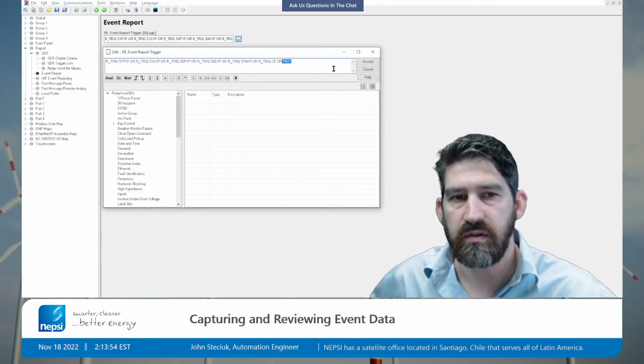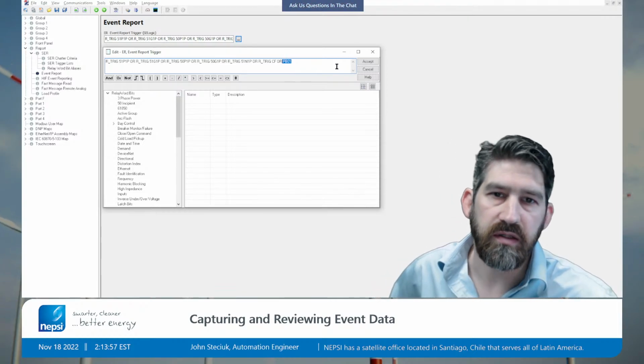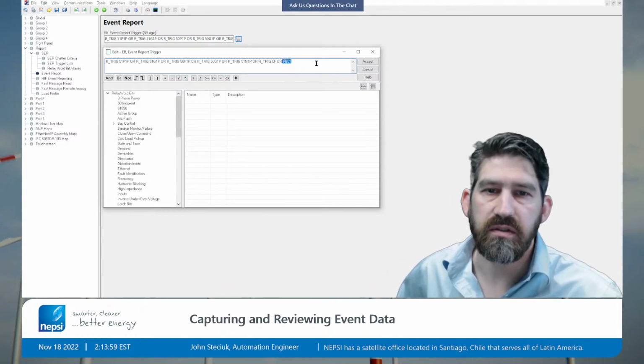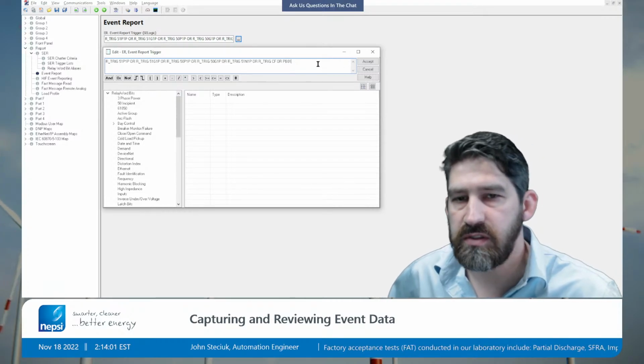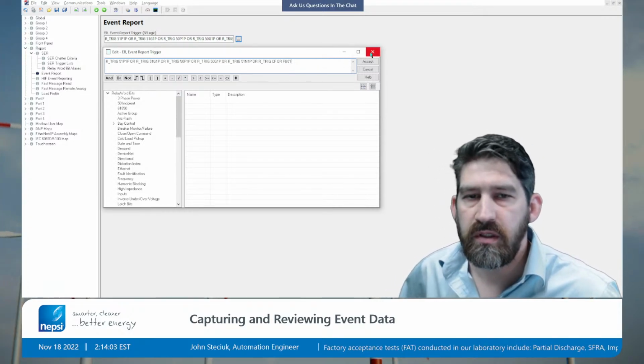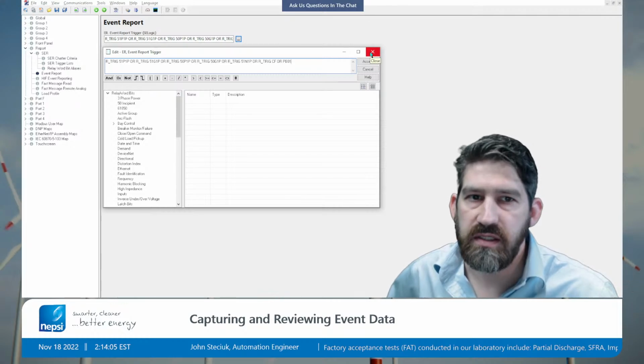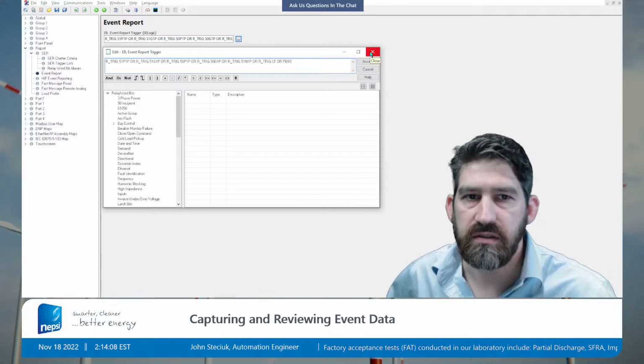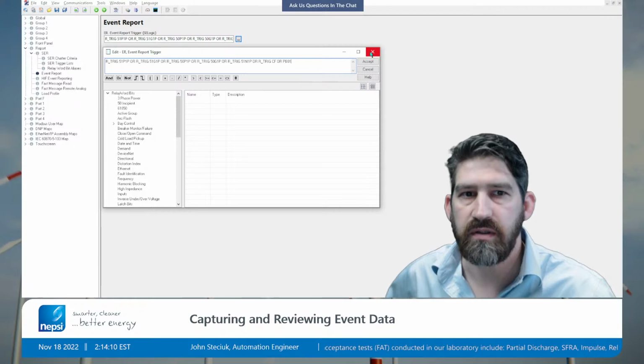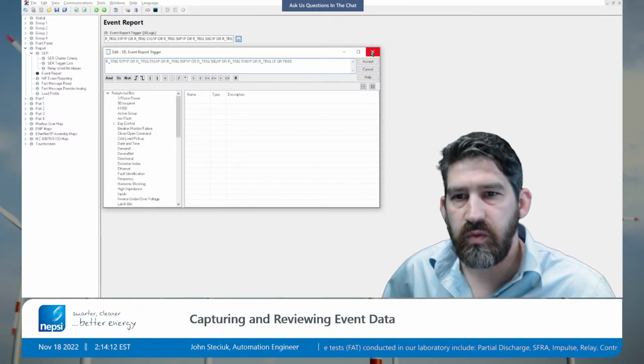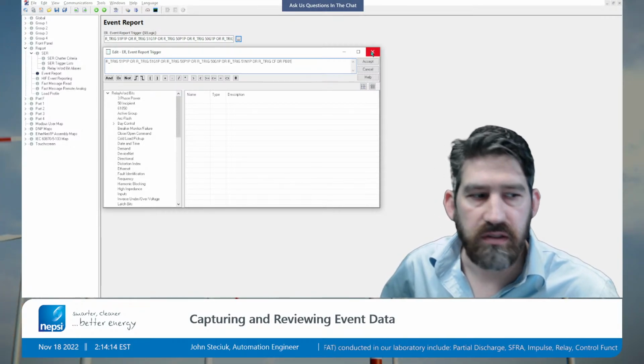So depressing the push button on the front of the meter will allow you to trigger an event report. There are also menus in the SEL relay that allow you just to trigger an event report there. So if you wanted to trigger something on demand, that's how you would do that.